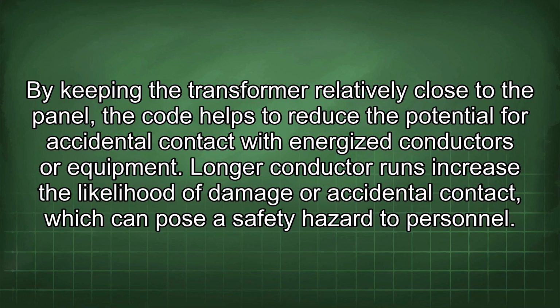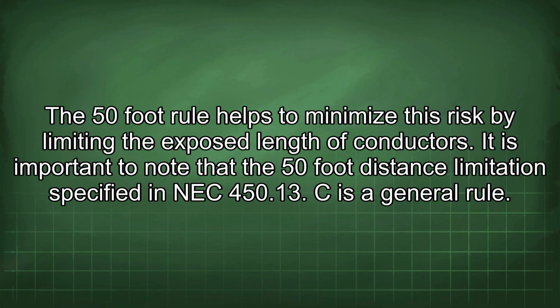In addition to voltage drop and conductor protection, the NEC distance limitation also considers overall system safety. By keeping the transformer relatively close to the panel, the code helps to reduce the potential for accidental contact with energized conductors or equipment. Longer conductor runs increase the likelihood of damage or accidental contact, which can pose a safety hazard to personnel. The 50-foot rule helps to minimize this risk by limiting the exposed length of conductors.